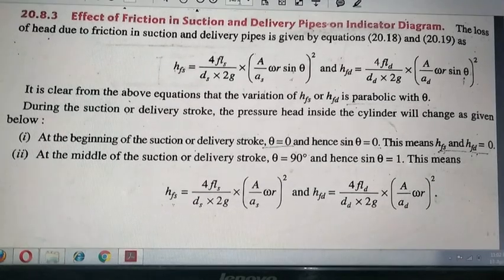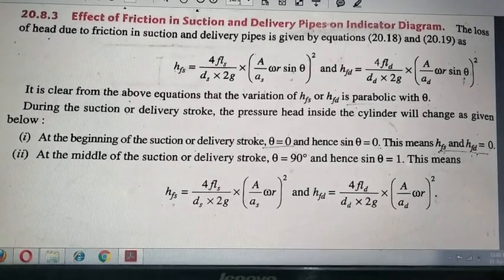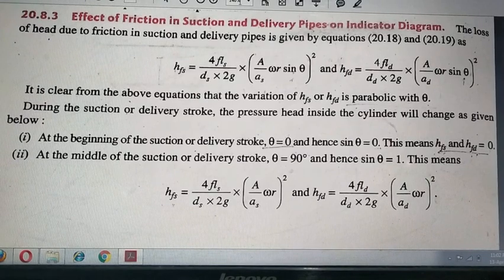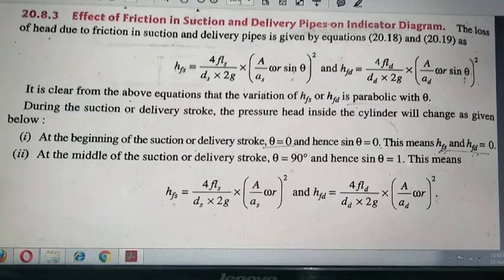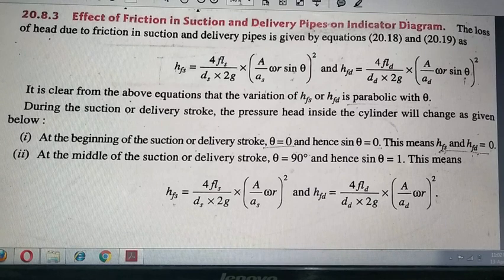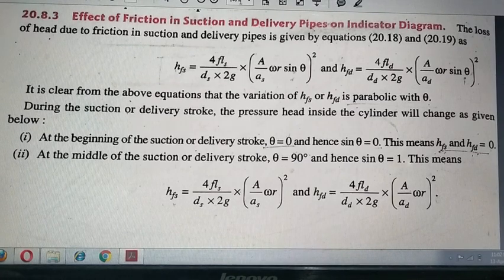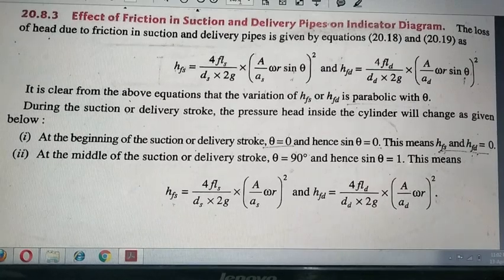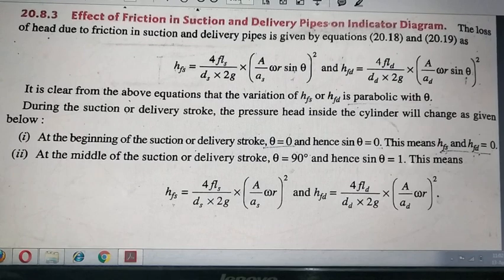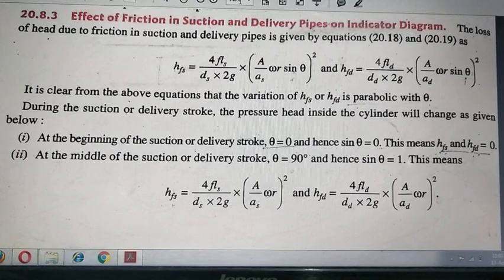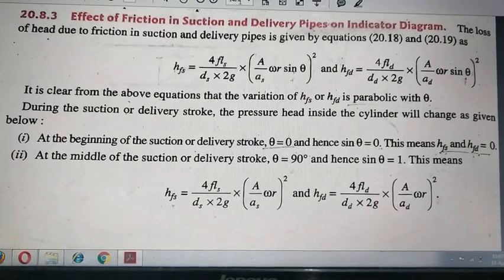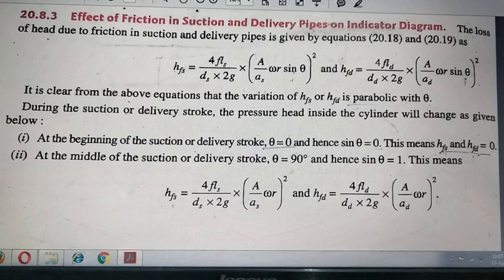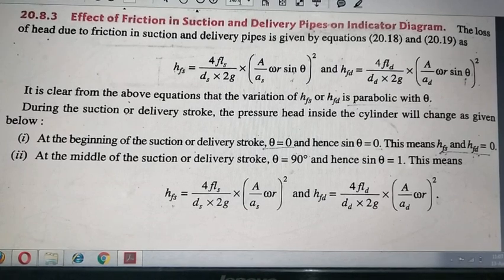Hello friends. In the last lecture we discussed the effect of acceleration head on the ideal indicated diagram. Now if we consider another effect — friction in suction and delivery pipes on the indicated diagram — we need to calculate the friction head. That is the friction head Hf, given by the Darcy equation: Hf = 4fLV² / (2gD).